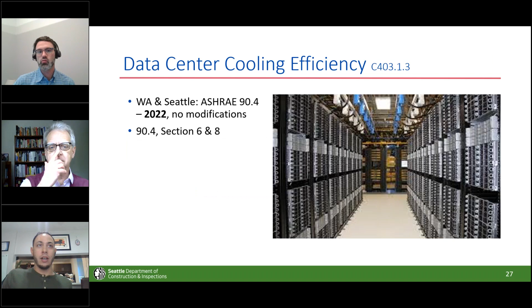Yeah, so the demand response, that's required demand response signals to slightly set back heating and cooling. This is in C403, but we're also going to talk about it in C406. If you're the right type of system, you could be required to set back room set points on a demand response signal, but you could also be required to set back loop temperatures. So you'd make your chilled loop slightly warmer, or your boiler loop, if you're a heat pump based boiler, slightly less warm. So it's there, but it's only on really large systems. I don't remember the threshold. I have to go look it up. Contact me after if you want to geek out on that further.